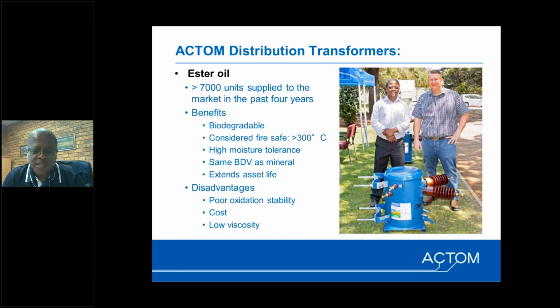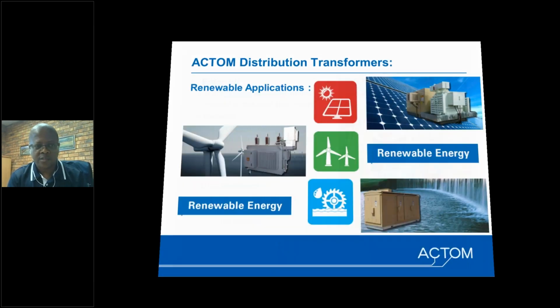The disadvantage about the ester oil is that it's got a poor oxidation stability. It's a little bit more costly than the mineral oil, and it's got a low viscosity. But we've got ways of handling it, and with the increased temperature, the viscosity issue is resolved. So it's a good oil to consider if the transformers are going into sensitive areas or areas where they can be subjected to abuse in overloading.